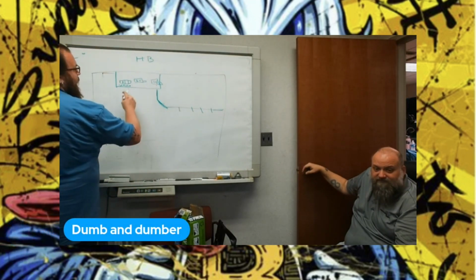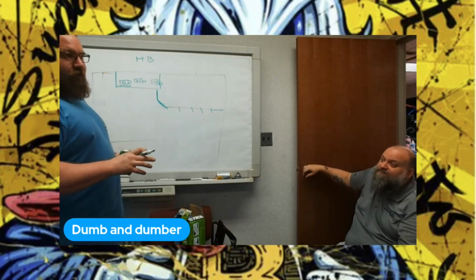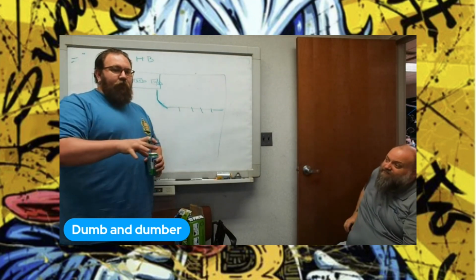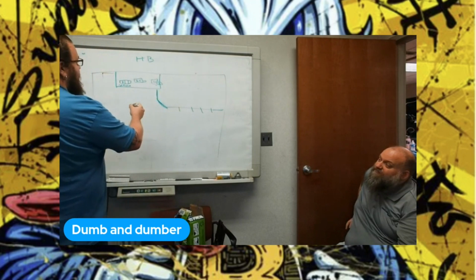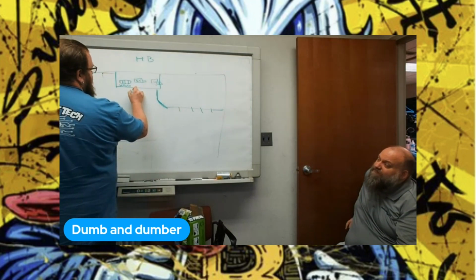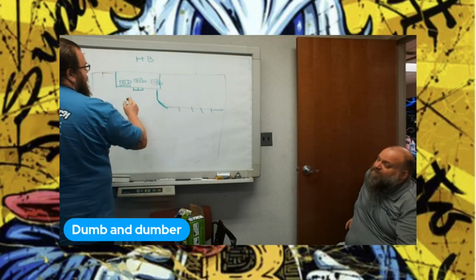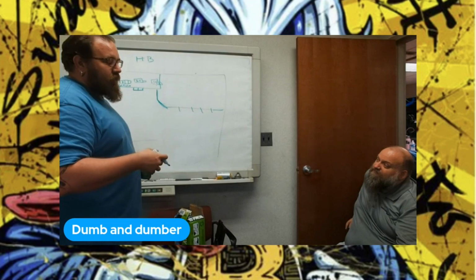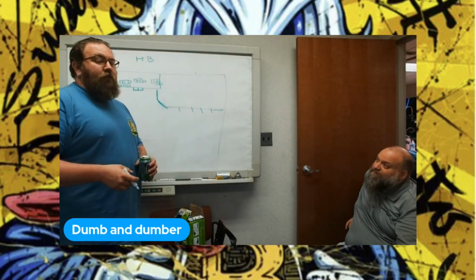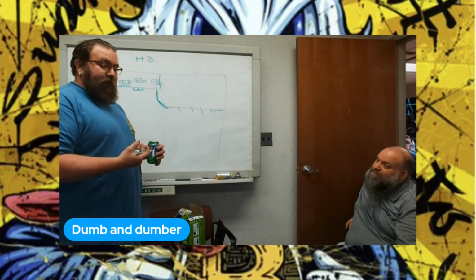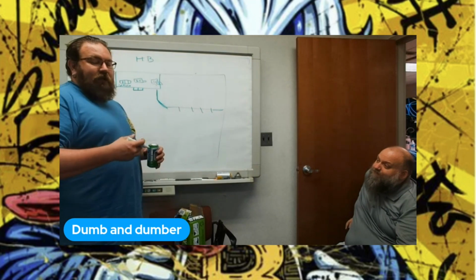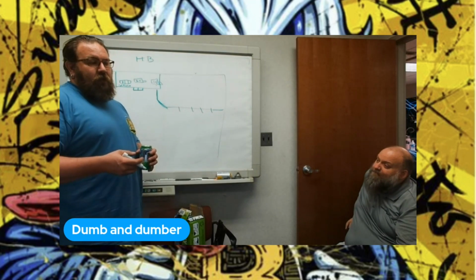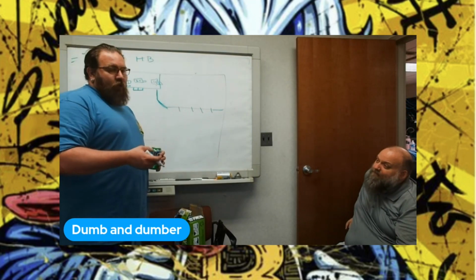From the 3500, we have barely scratched the surface of that transformer on the low bay side. The only thing we've really pulled off of it are 2 208 volt—actually we've retapped these transformers. They came out of a former data center, and Fred retapped these transformers and PDUs closer to 220.